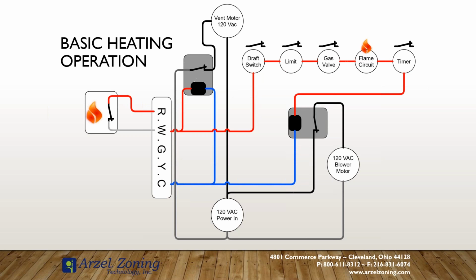So on a call for heat, I close W. That then starts my vent motor. My vent motor operating closes my draft switch. So that proves that my vent motor is running now. With my draft switch closed, I'm looking to make sure that my limit switch is closed. While those happen simultaneously, this is kind of a sequence of operations, but a lot of these things happen at the exact same time. The check is happening at the exact same time. And if any one of them fails, my heat does not run.